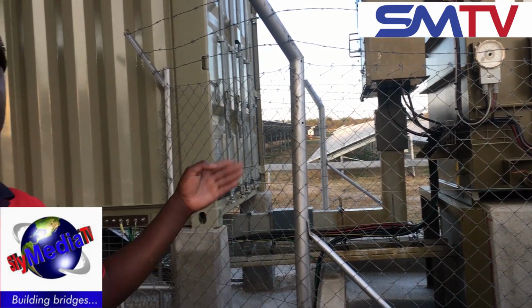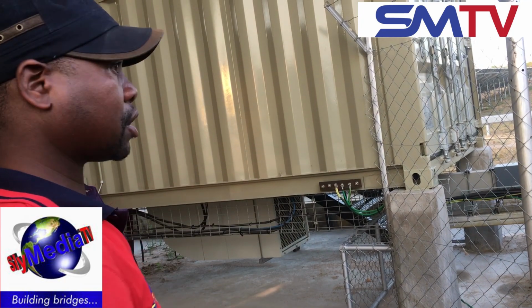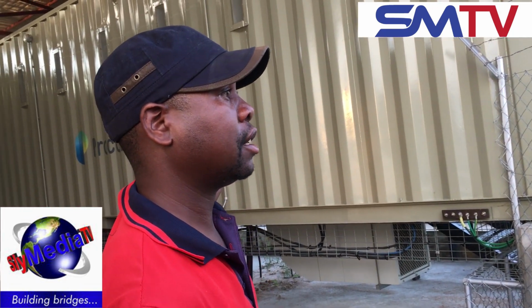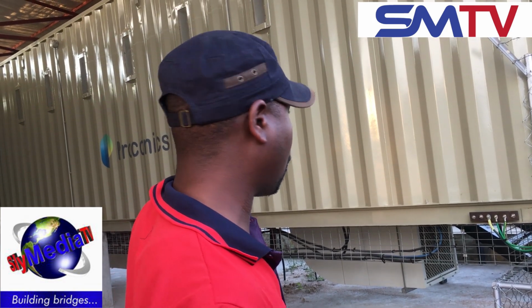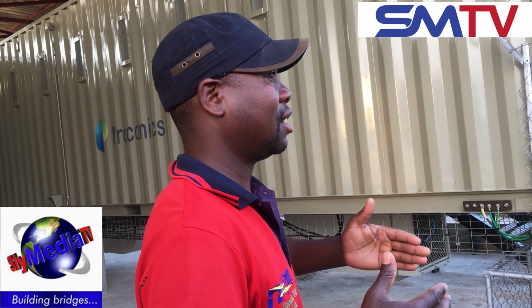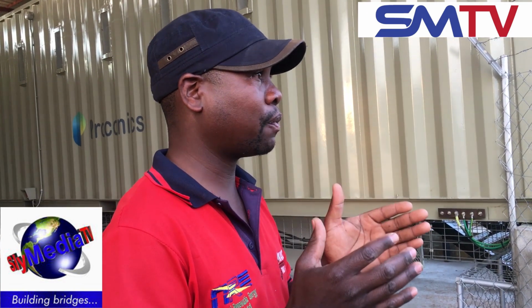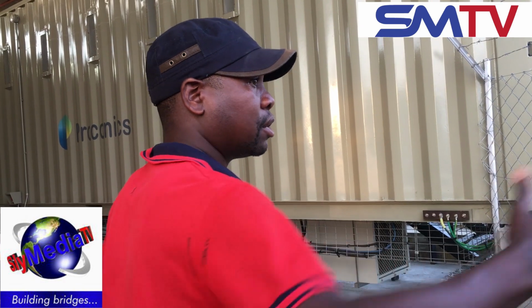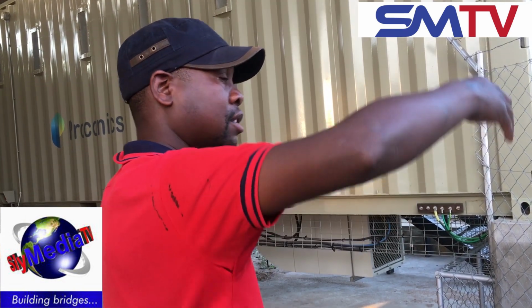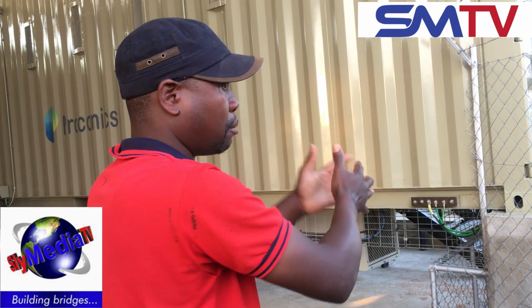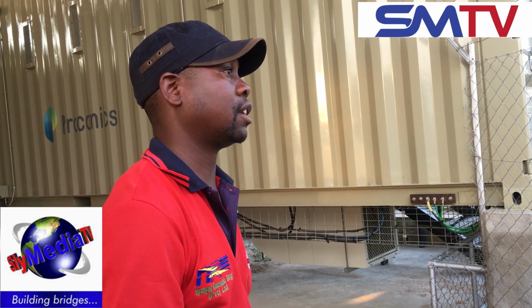Then these two—we've got our RMU inside, which combines these two transformers. It's also our substation, where we've got a 33 kV breaker, an isolator, and an earth switch. In other words, it's our gas insulated substation, a GIS. Instead of building a very big substation with large CTs and VTs, everything is combined into a small unit.